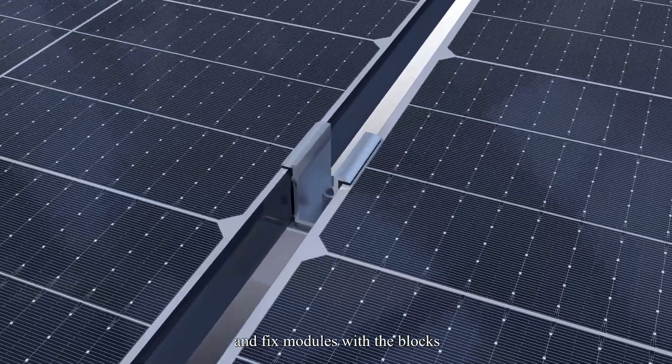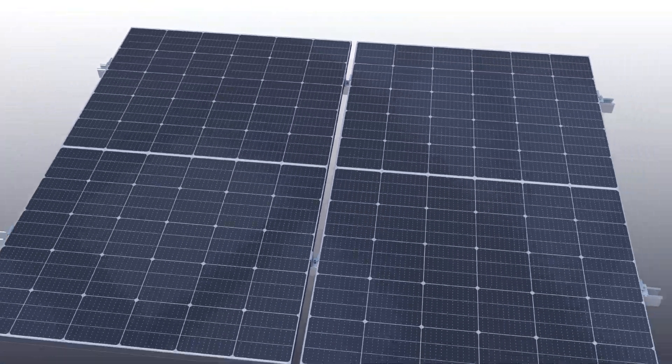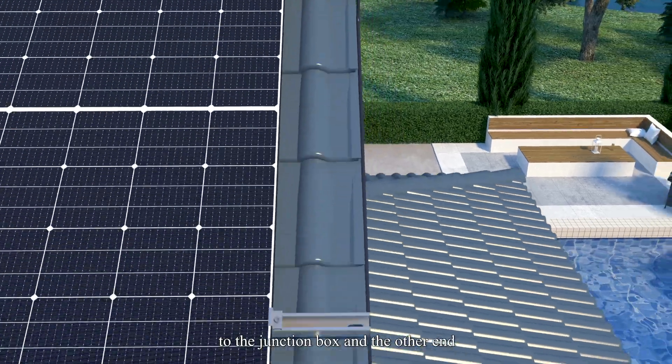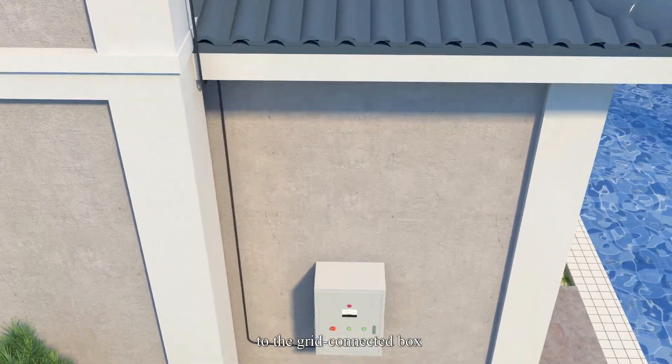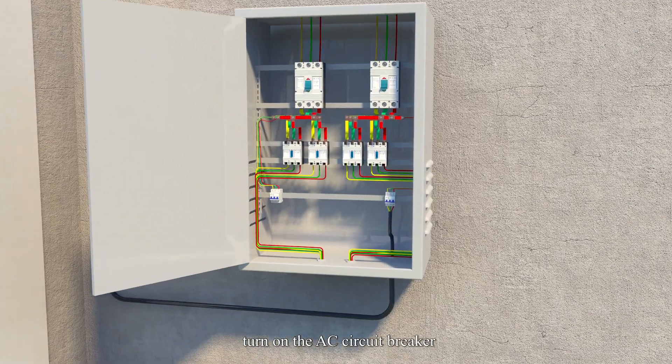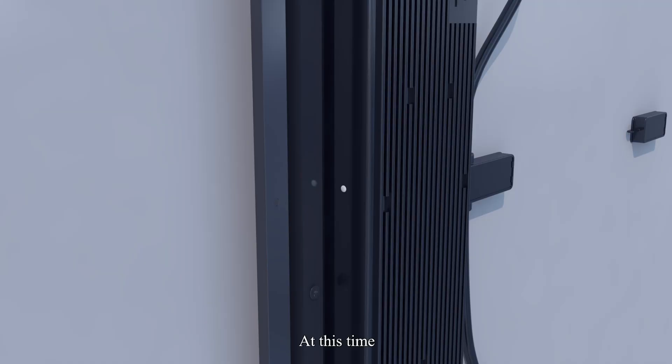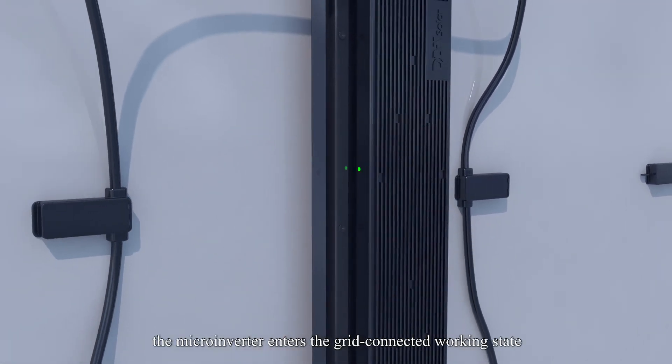Fix the modules with the blocks. Step 5: System Grid Connection. After connecting one end of the extension cable to the junction box and the other end to the grid-connected box, turn on the AC circuit breaker. At this time, the indicator light of the microinverter switches from flashing red to a flashing green indicator. After about one minute, the microinverter enters the grid-connected working state.